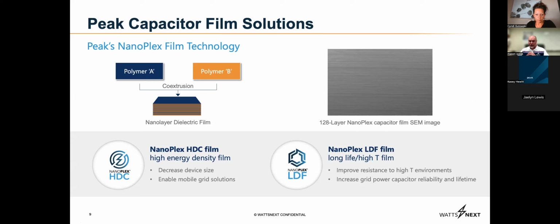So on the right-hand side here, you can see an internal structure of a film. This is a 128 layer film with alternating layers of two polymers that have different thermal, dielectric, and mechanical properties. And depending upon which materials we put into our nanolayered films, we can completely and totally tune and change the property sets. So at present, we have two different families of film. One is the NanoPlex HDC film. This is a high dielectric constant film, and this is designed specifically to deliver very, very large charge storage in very small devices. And then we are developing another family of film called NanoPlex LDF, and this is designed to mimic the electrical properties of BOPP, but do so at higher operational temperatures.